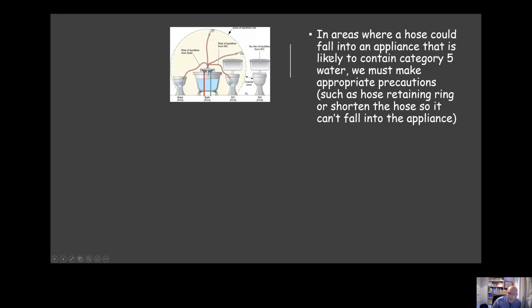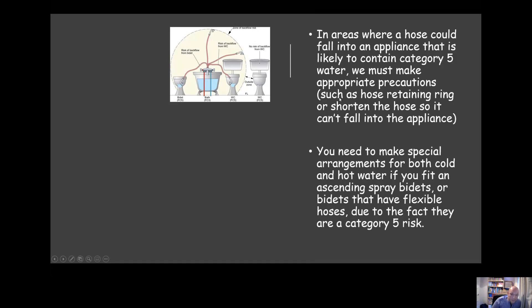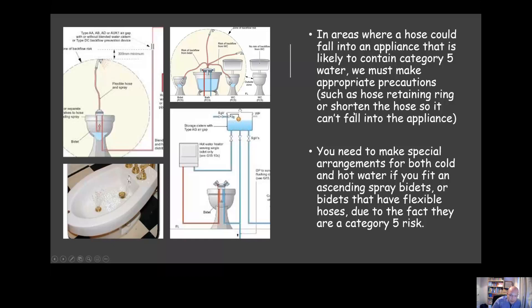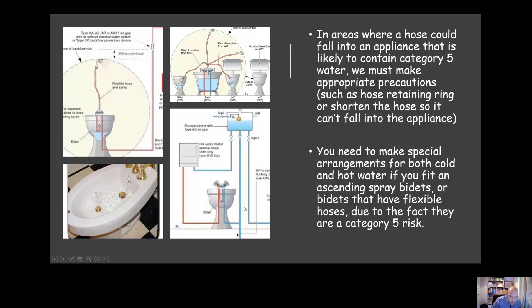In areas where a hose could fall into an appliance likely to contain category five water, appropriate precautions must be taken — for example, using a hose retaining ring or shortening the hose so it can't fall into the appliance. Worth noting: if you have an ascending spray bidet or any bidet with a flexible hose, you must not feed that appliance from the mains. You can feed it from storage, as long as it's the only appliance fed from that run, ensuring there's no chance of water being sucked back into the system.